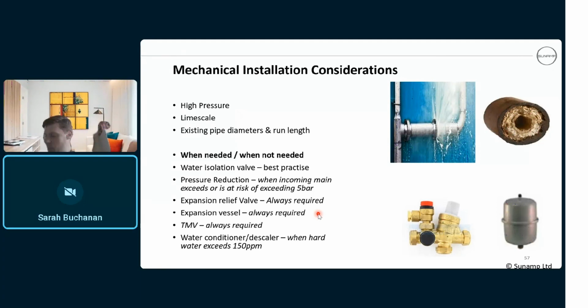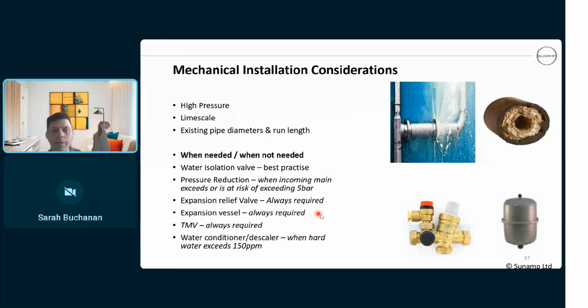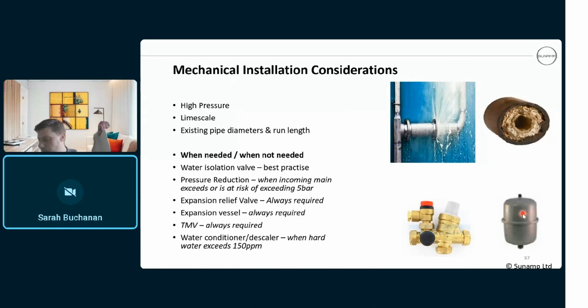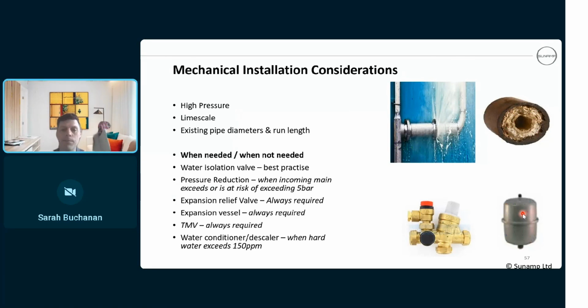Exactly. And what should that pre-air charge in the vessel be? What do you think that should be charged to? What pressure? The same as the PRV? The same as the incoming mains pressure supply. So if you've got your pressure reducing valve set to 3.5, that's what your air charge should be. I mean, these are pre-charged to 3.5 bar anyway, or they should be, and that's another point to consider as well. How long has that vessel been sitting on the shelf at the stockist? So always check your vessel's got the correct air charge in it.